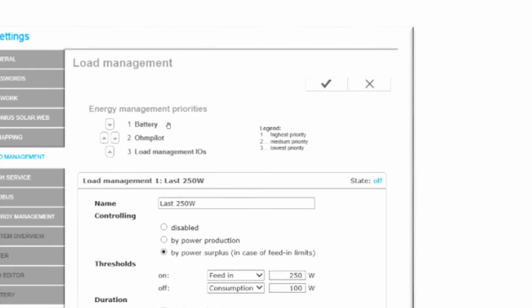And if the battery is satisfied as far as charging is concerned, then the Ohmpilot takes priority number 2 to utilize the excess energy. And if the water temperature has been achieved, then the management of loads through the IOs will be priority number 3. Of course, if you do not have a battery system or an Ohmpilot and you want only to use the management IOs, digital IOs, then you can flip this over so that you have the load management IO as your priority number 1 for using the excess energy.